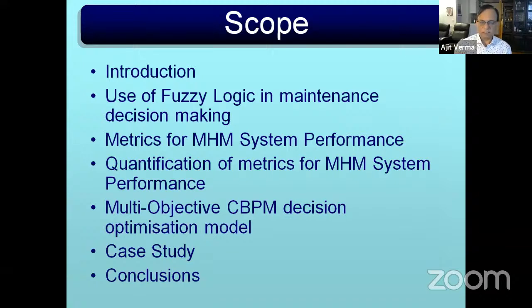Based on the condition of the system, how it changes state from one to another, you track metrics such as pressure, flow, temperature, vibration, current, and so on. You trend these parameters, and when they cross certain thresholds, predictive analytics project that failure will occur at some time, and just before that you carry out maintenance, based on the condition of the equipment and the condition of the plant.